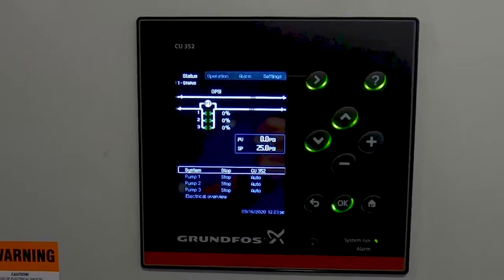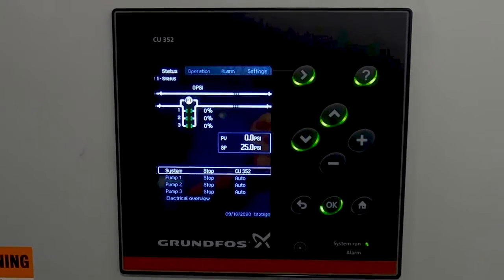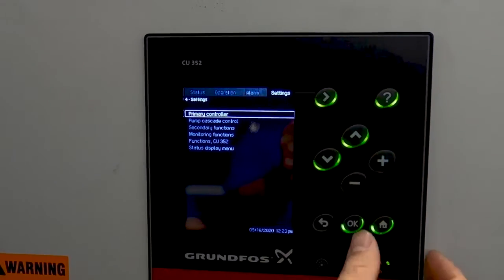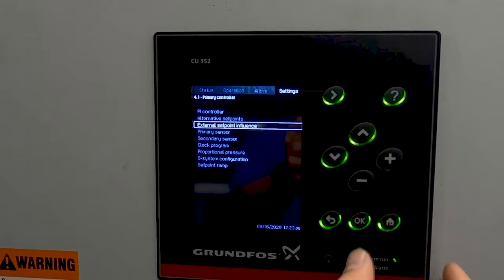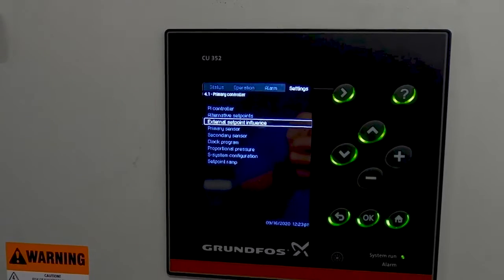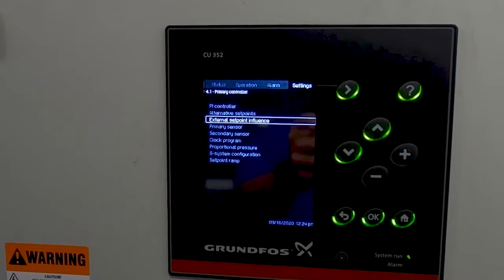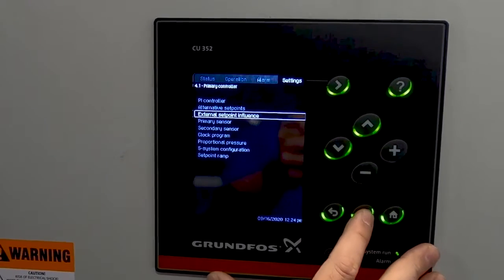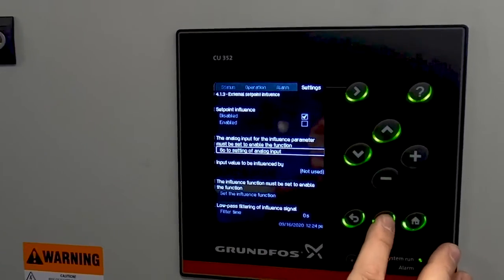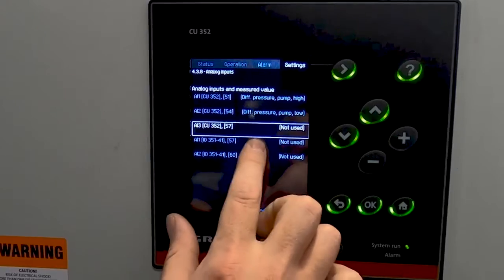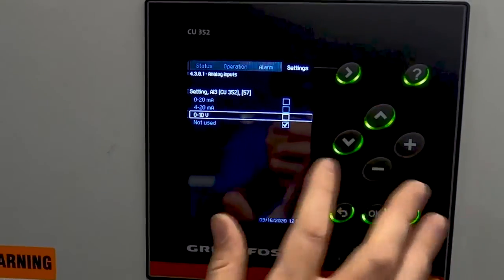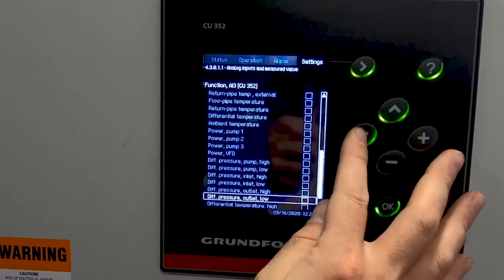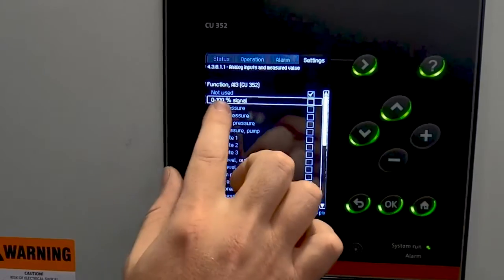Some engineers may require that a zero to 10 or four to 20 signal is sent to the controller to maintain set point. To do this, you use the set point influence — go to settings, primary controller, external set point influence. Whatever set point you have programmed in the controller, the zero to 10 or four to 20 is enabled to adjust it up and down based on system requirements. You can also do this through BACnet, but this is based on sending an analog input. To get started, pick your analog input — we're going to pick analog input three. For ours, it's going to be a zero to 10 volt system, and the input value to be measured is going to be from zero to 100% signal.